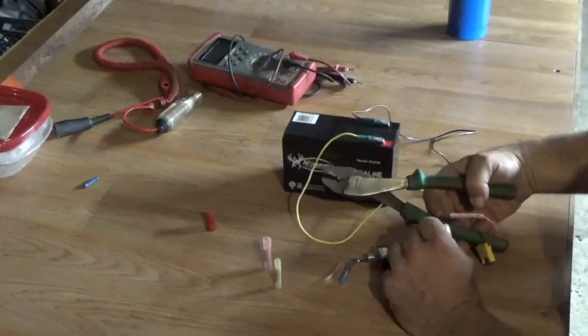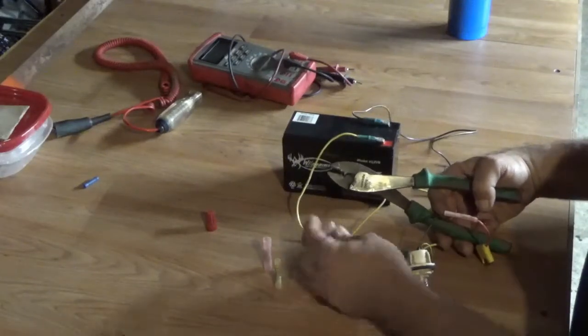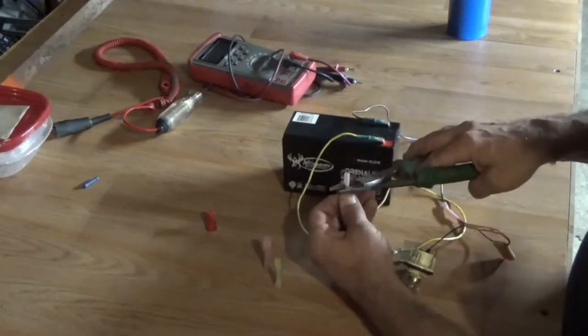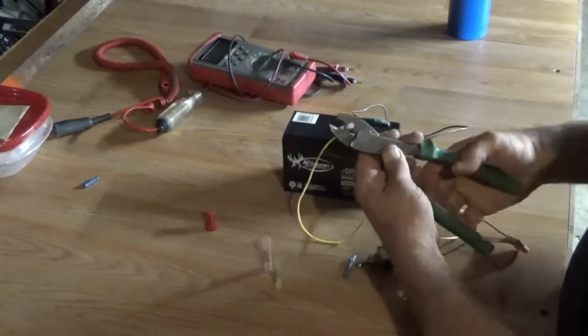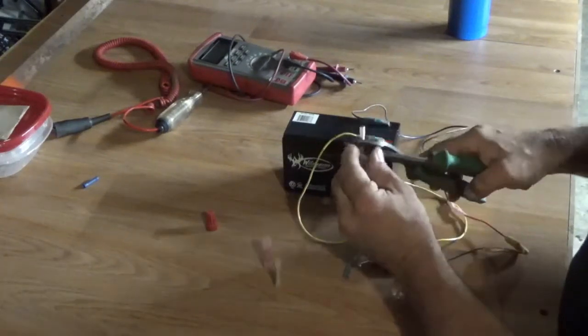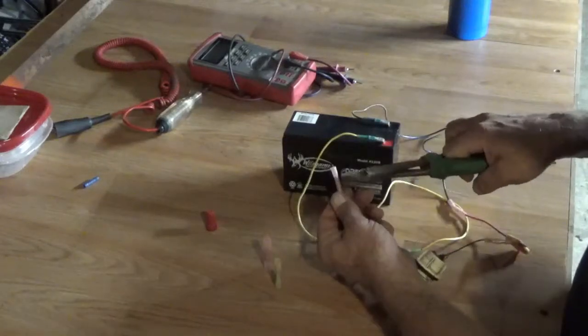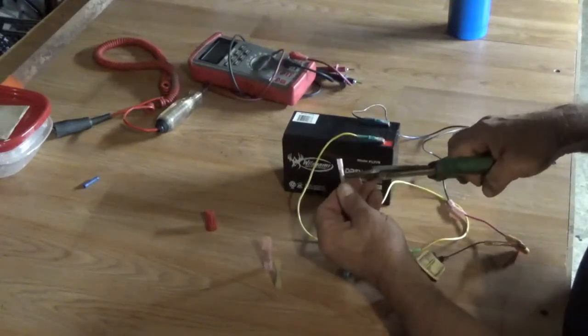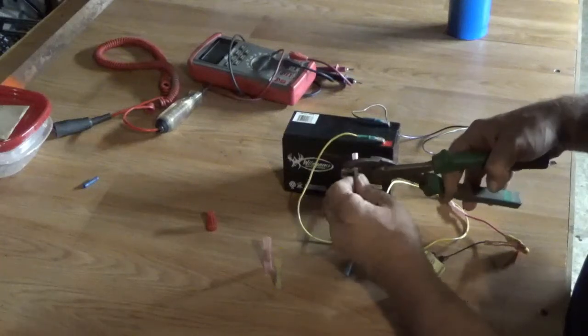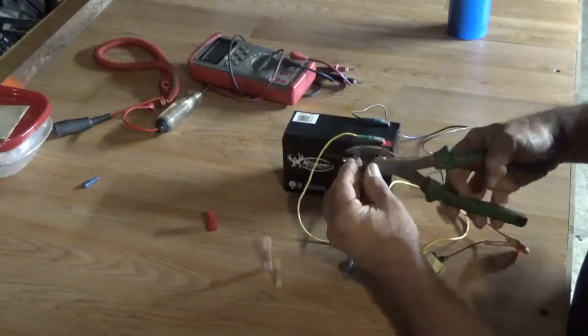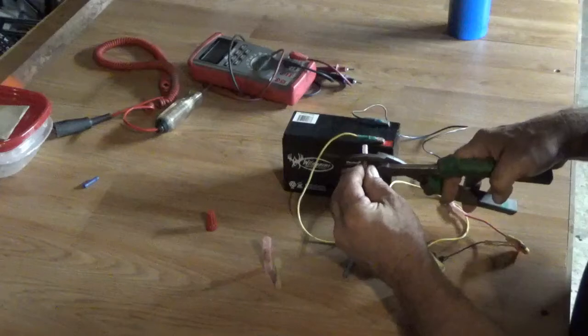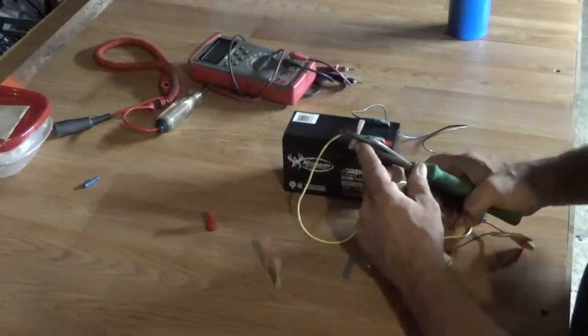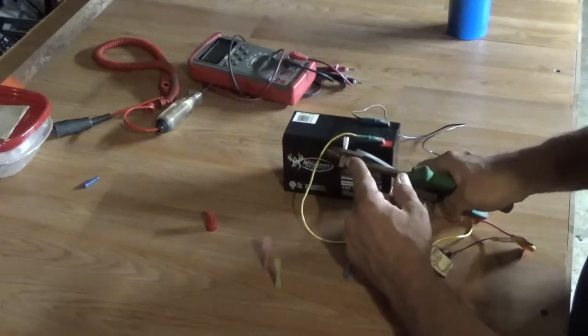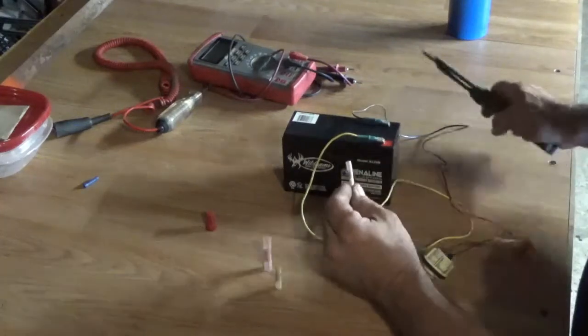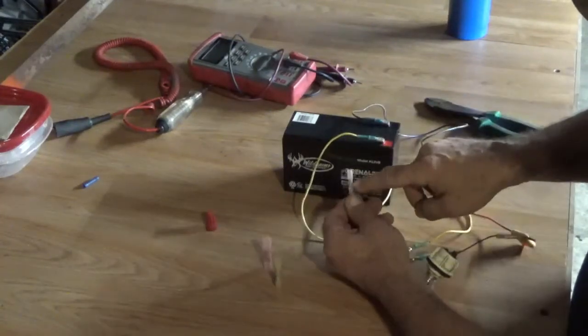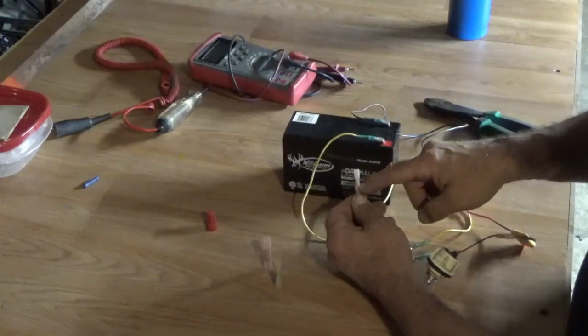These are the crimper strippers that I use. To crimp one of these connectors, I usually go right to the end of the metal. If you look inside or through it, you can see there's a metal tube in here, and your wire is going to go halfway into that metal tube. There's a stop in there, so you don't have to worry about going too far. I usually go down as low as I can on the metal tube and then squeeze it. But you don't want to squeeze it so hard that you penetrate this plastic - that will cause a leak.